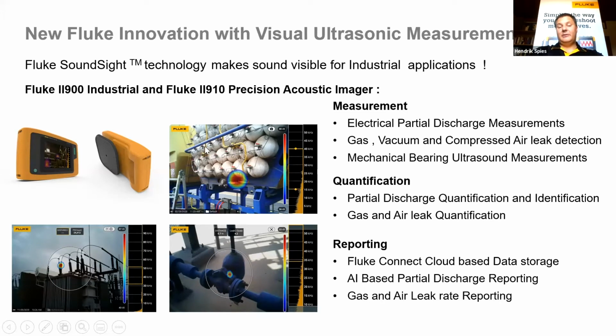We can do it for any type of asset, like this is a natural gas leak on a storage facility. And what is very good about our technology, we can quantify as well. So why is this product good? Number one, we've got SoundSight patented technology from Fluke in the industrial imager, which is the II900 or the II910, which is a precision acoustic imager, very sensitive. We can then detect partial discharge, which is typically electrical-based discharge. We can then detect gas, vacuum, and compressed air leaks. And as you'll see later, we can also do mechanical bearing ultrasound. So any sound-based detection can be done with this ultrasonic precision acoustic imager.